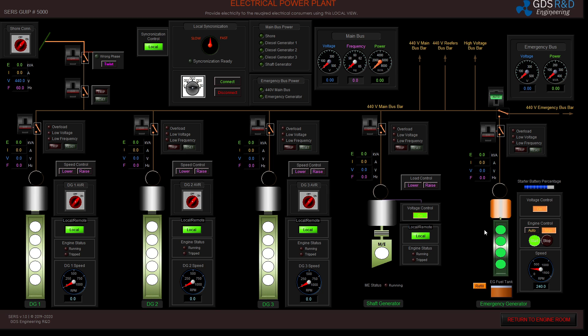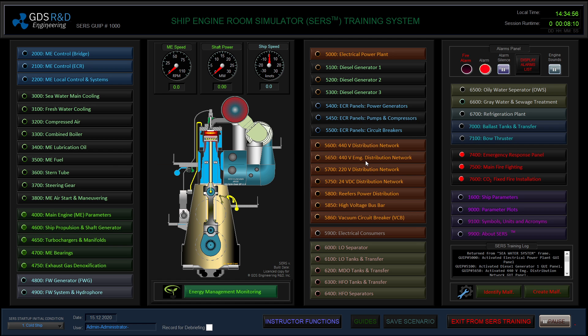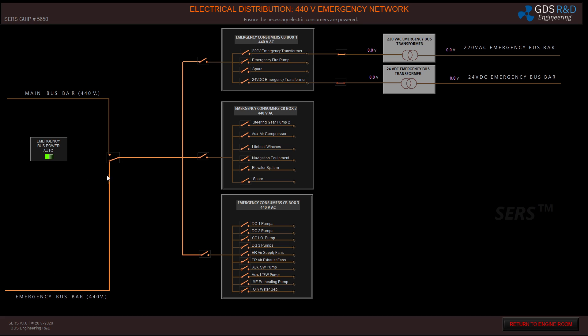I am going to start the emergency generator in manual mode. I am waiting for the engine speed to reach up to 720 RPM. I have connected my emergency generator to the emergency bus bar. I am not feeding my main bus bar, but I am feeding my emergency bus bar from the emergency generator.